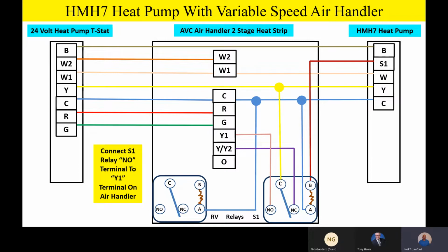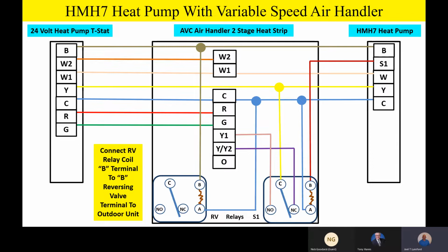And so the air handler has to see an O signal in the cooling mode on a heat pump for some advanced functions, like dehumidification is one of them. Another advanced function is the cooling on delay function. So all that's driven by the O signal. So the other side of the RV relay coil goes up to B terminal. So when this unit's in the cooling mode of operation, you'll see that the normally closed contact and common is going to grab 24 volt off of yellow, just like we did before. But the normally closed contact on the RV relay is going up to O terminal.